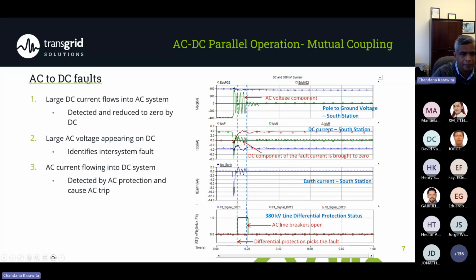if these kind of faults happen, there is a very large DC current flow into the AC system. So we need to detect this and reduce it to zero. And this is usually done from the HVDC side. Similarly, there is a large AC voltage appearing on the DC. So you can see the huge AC component appearing on the DC lines. So, and we need to detect this and control this as quickly as possible.